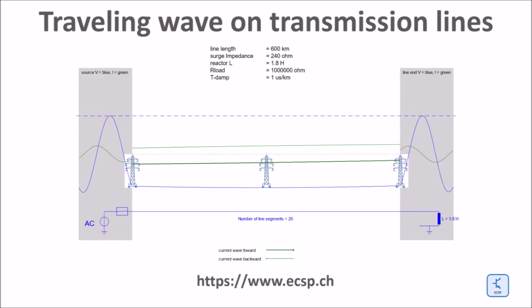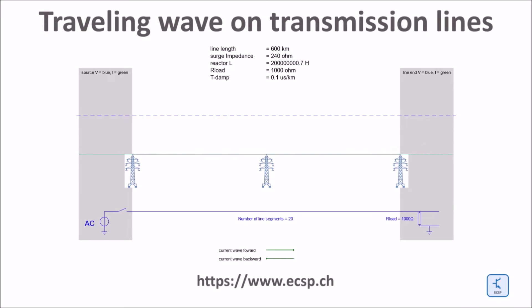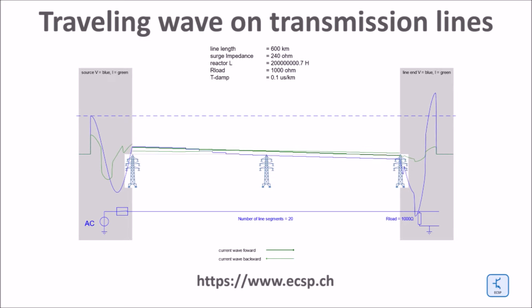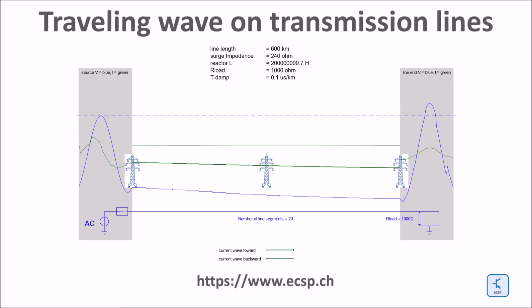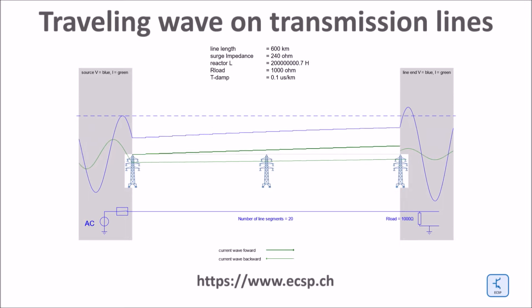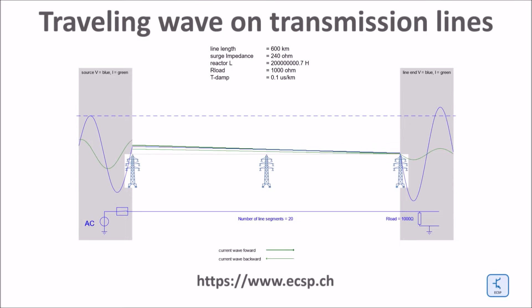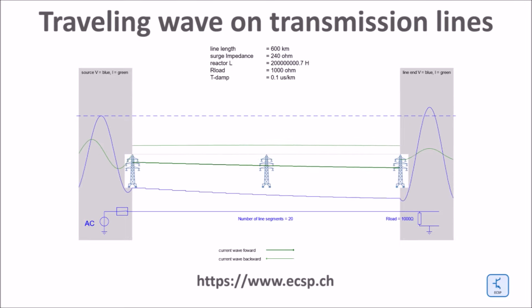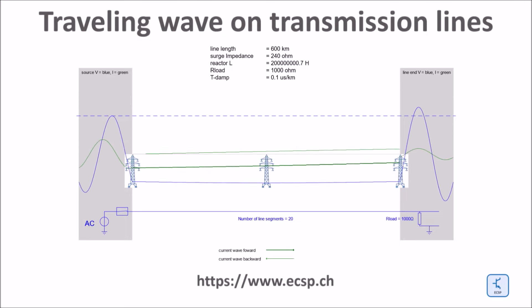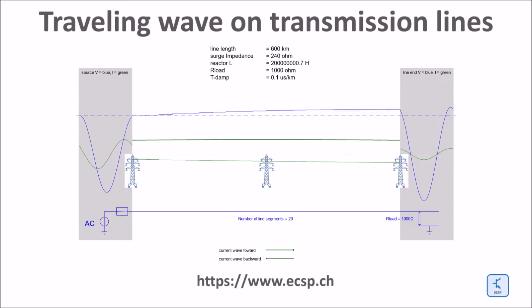Next I replace the reactor by a 1 kilo-ohm resistor, which is significantly higher than the surge impedance of the line. As a result, I still get some overvoltage but much less than operating the open end line as shown before.